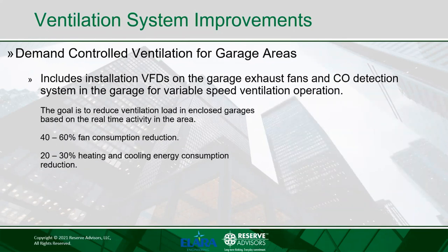Demand control ventilation for garage areas is a very similar concept. The goal here is to reduce ventilation load in enclosed garage spaces based on real-time activity in the garage. Energy savings associated with these systems are more significant if the building has a heated, enclosed garage. The system would basically utilize carbon monoxide sensors and detectors to track garage activity, and equipment providing ventilation for the garage space would be controlled accordingly to save energy. With these types of upgrades, similar energy savings would be expected, 40 to 60% fan energy consumption, depending on system details, and 20 to 30% heating energy consumption reduction.